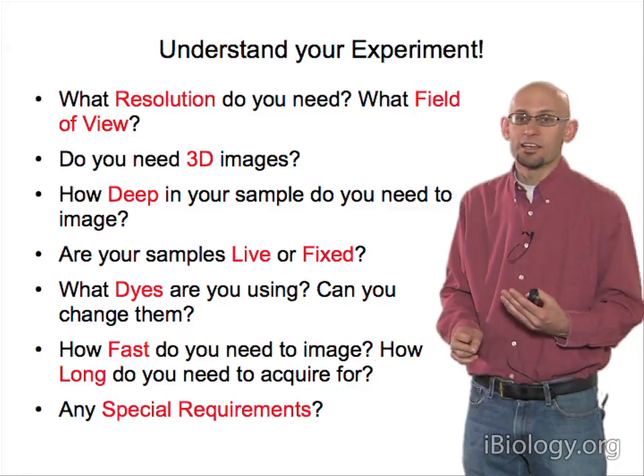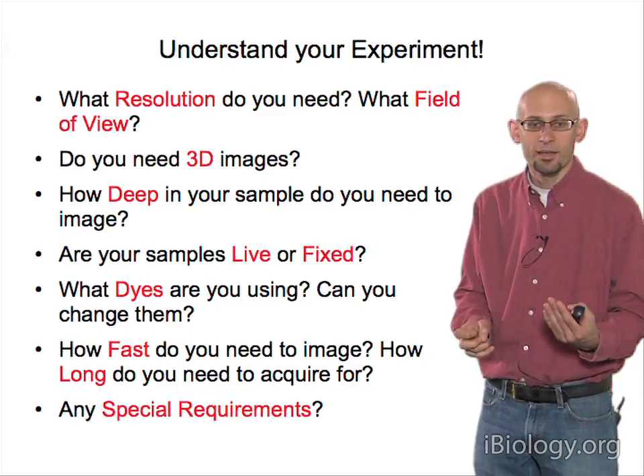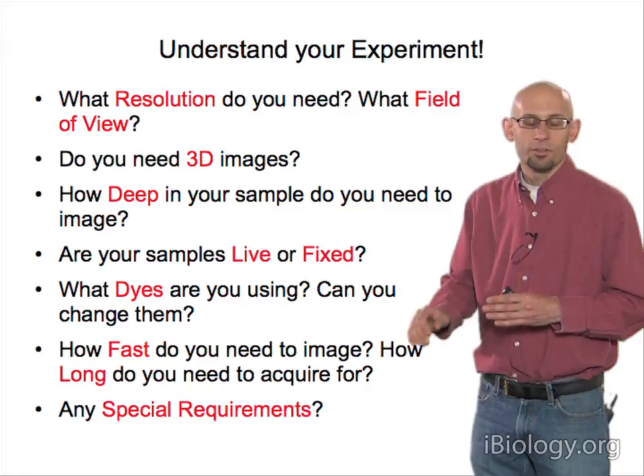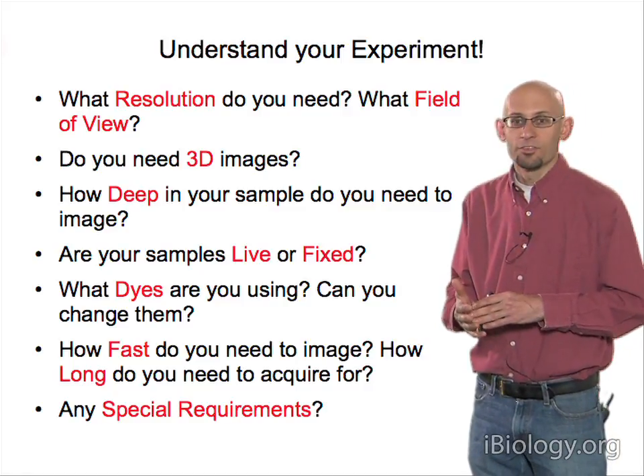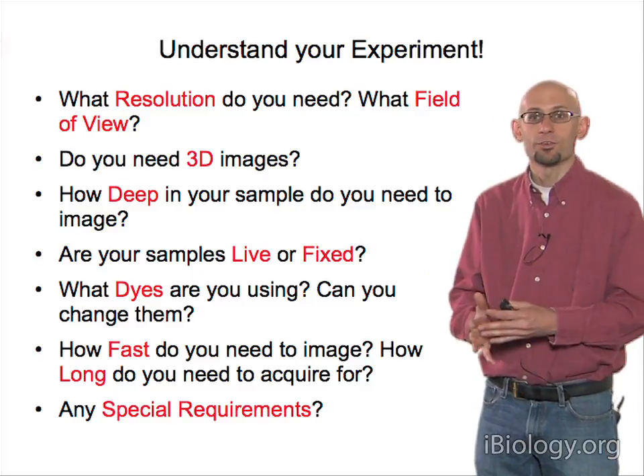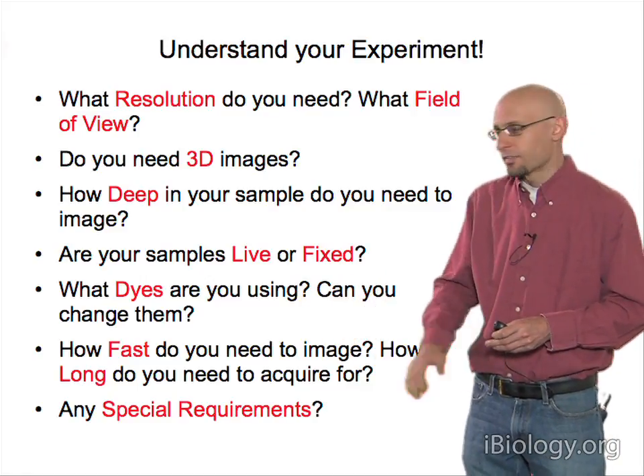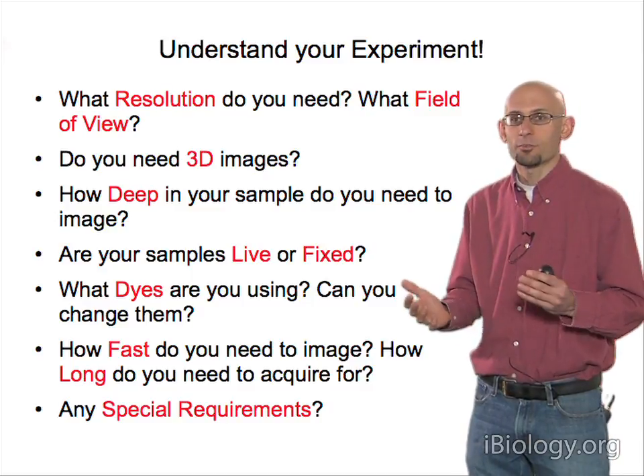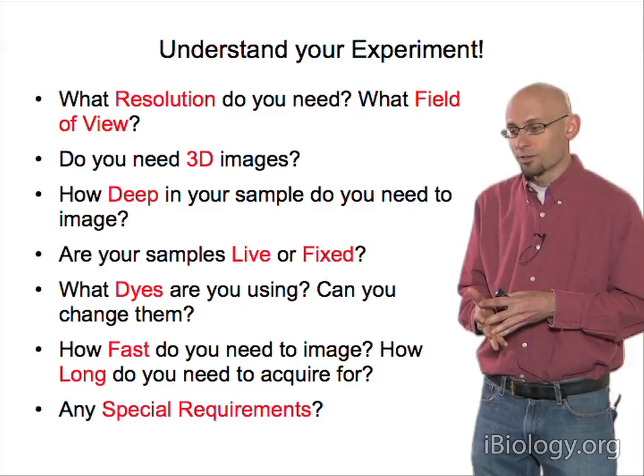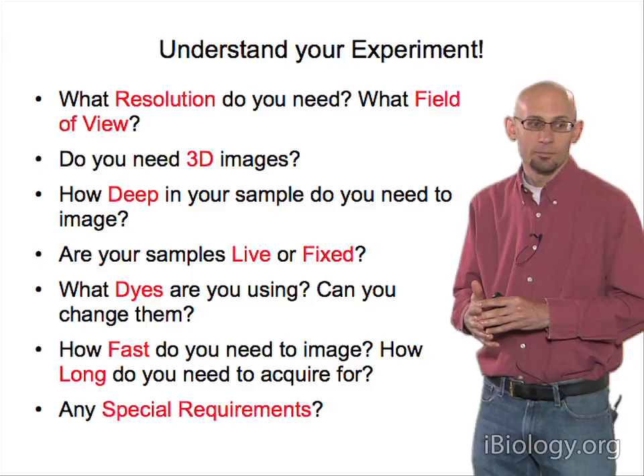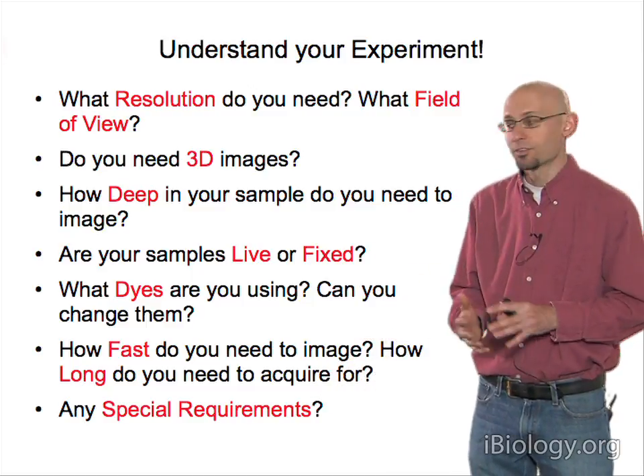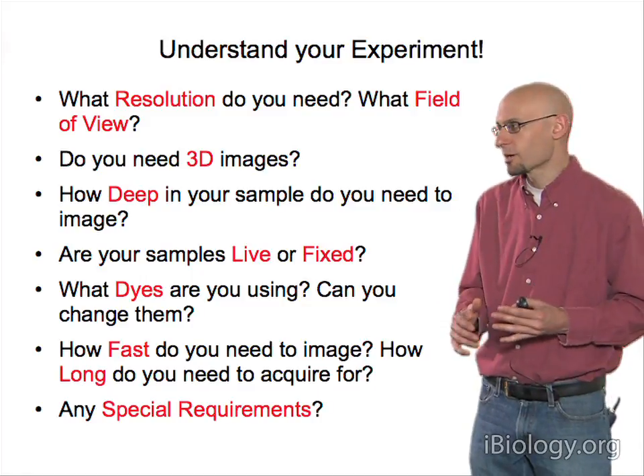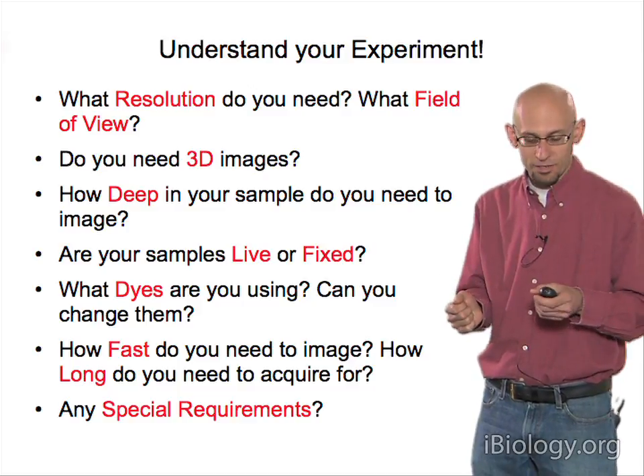You also want to know how fast you need to image. Are you trying to take video-rate data in real time, doing long-term time lapse, or just single time-point imaging? There will be trade-offs as to which microscopes can go quickly, or have facilities for preserving cells alive over 12 hours and holding focus. Finally, are there special requirements — a FRET experiment needing the right filter sets, lifetime imaging, or single molecule imaging? Having some idea of these requirements will make it much easier to choose an appropriate instrument.